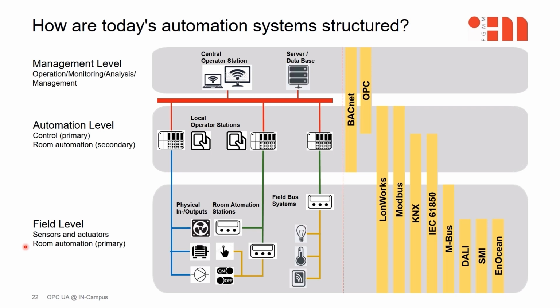Before I talk about the structure of the building automation system on the INCampus, I would like to take a quick look at the structure of today's building automation systems. The system structure generally has three levels. The lowest level is the field level, which contains sensors and actuators, as well as application-specific controllers, for example, for room automation or for controlling individual devices or systems. The automation level with the automation stations or programmable controllers is located on the middle level. This level is used to regulate and control the building systems and devices.